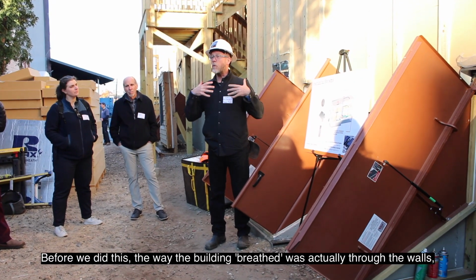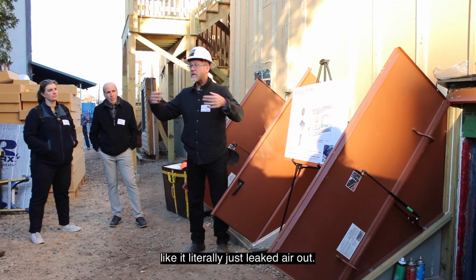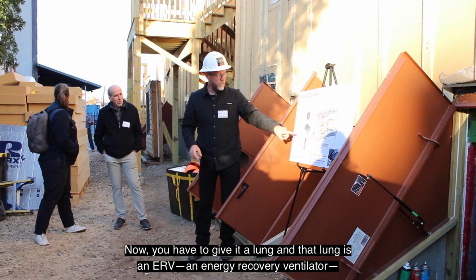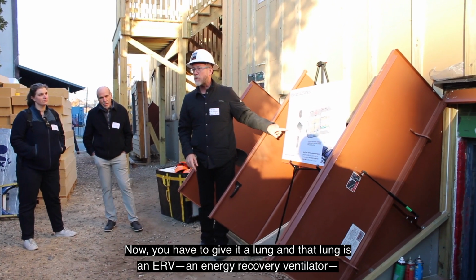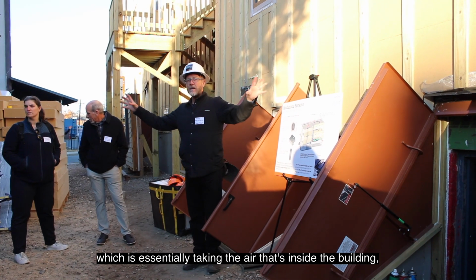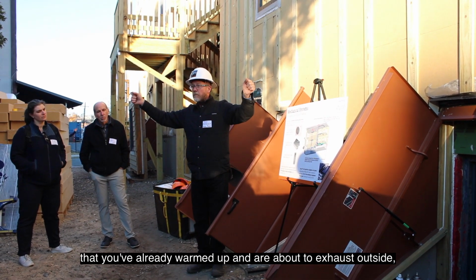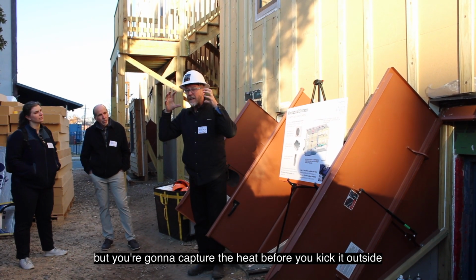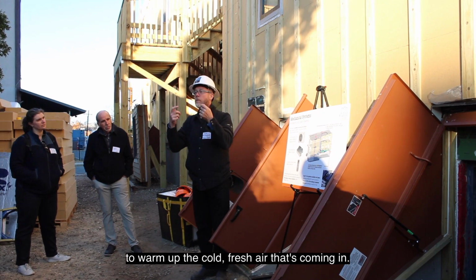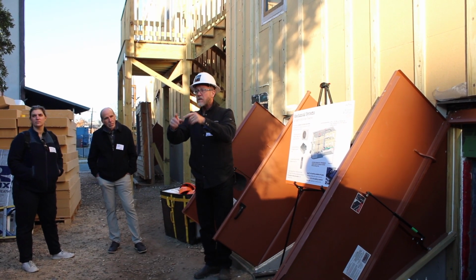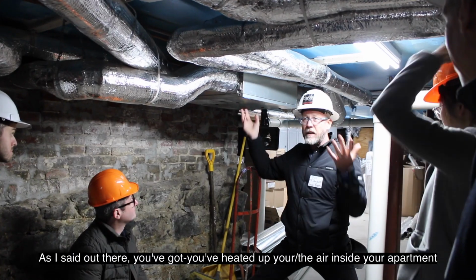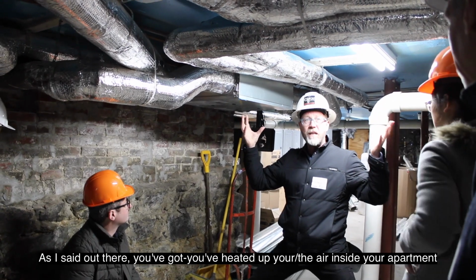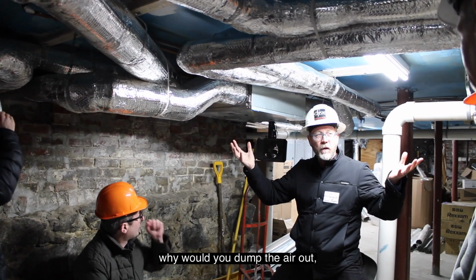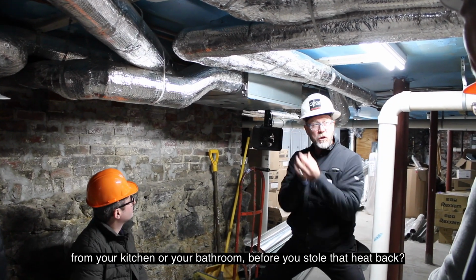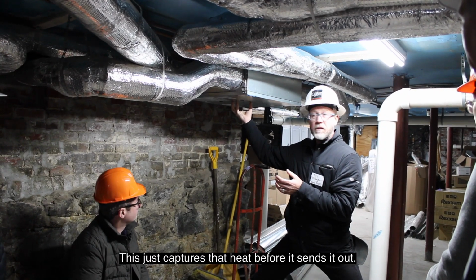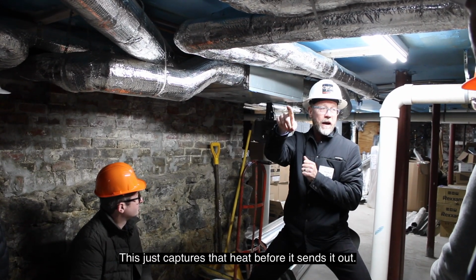Before we did this, the way the building breathed was actually through the walls. It literally just leaked air out. Now you have to give it a lung, and that lung is an ERV, an energy recovery ventilator. It takes the air that's inside the building that you've already warmed up and are about to exhaust outside, but captures the heat before kicking it out, to warm up the cold fresh air coming in. So it's an energy recovery lung. You've heated up the air inside your apartment, so why would you dump the air out from your kitchen or bathroom before you steal that heat back? That's all this thing does, it captures that heat before it sends it out.